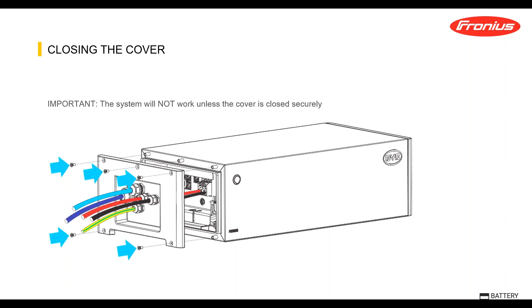And finally, commissioning. This is a simple addition to the installation process of batteries, just a couple of steps, but very important, especially connected with Fronius inverters. Make sure the inverter is off before you connect the battery. Switch on the battery, commission it, and then switch on the inverter. If not, you might get strange behavior, and the battery might not be able to finish the commissioning process.